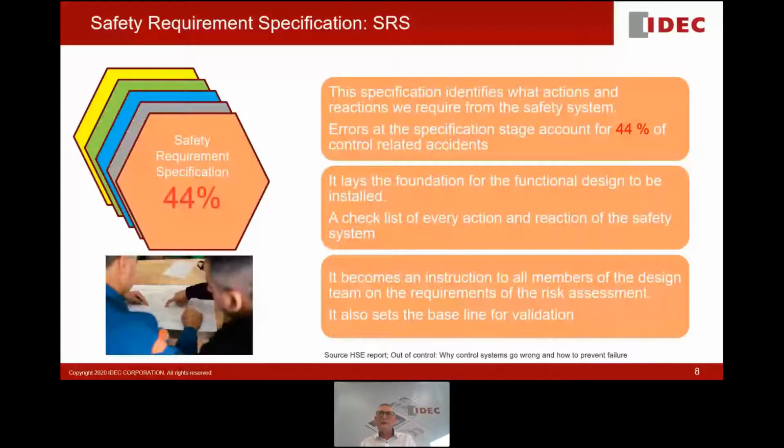And with that, the instruction goes to the members who build the machine up, and they then identify whether or not their design is going to meet the requirements of the risk assessment. And probably the single most important thing, it creates a baseline for validation. At the very end of this presentation, we will talk about the validation of the installed equipment. There is no point in creating a safety requirement specification if you do not validate that what you intended to do has been achieved.